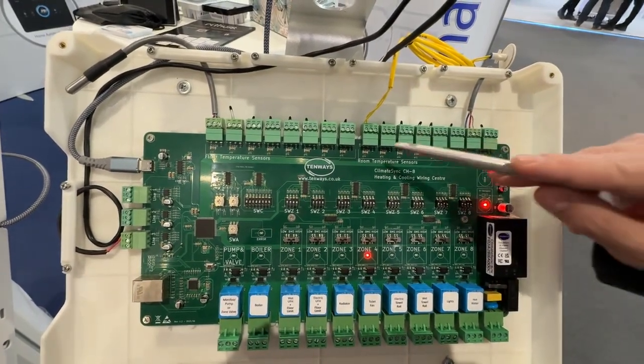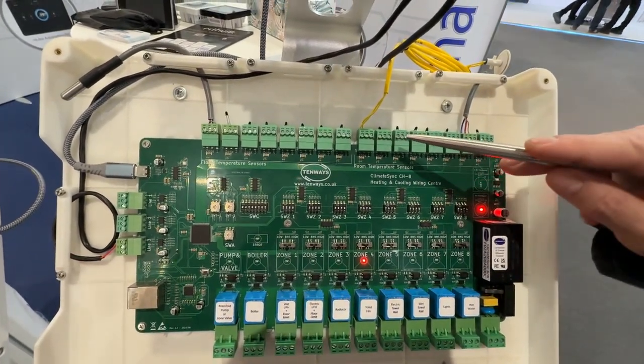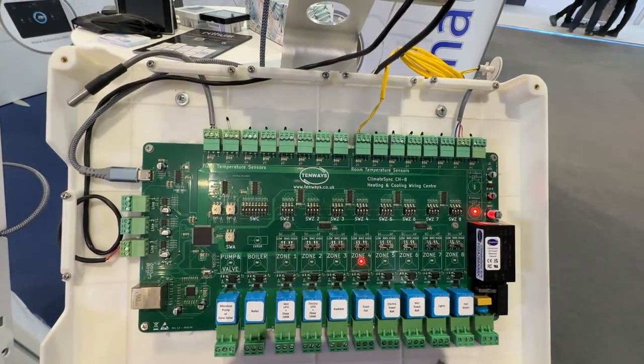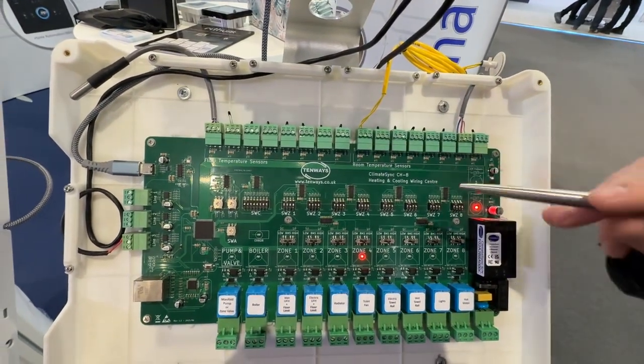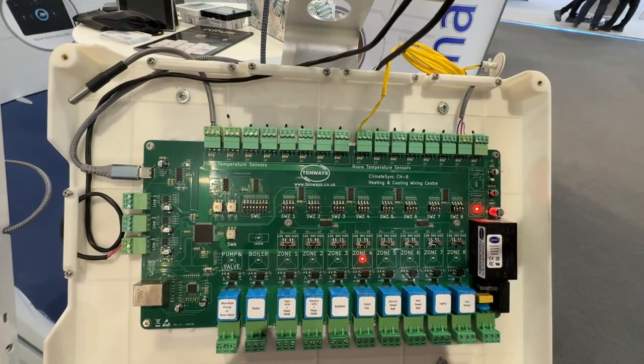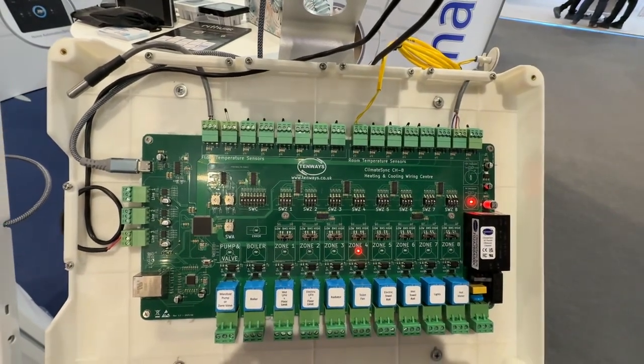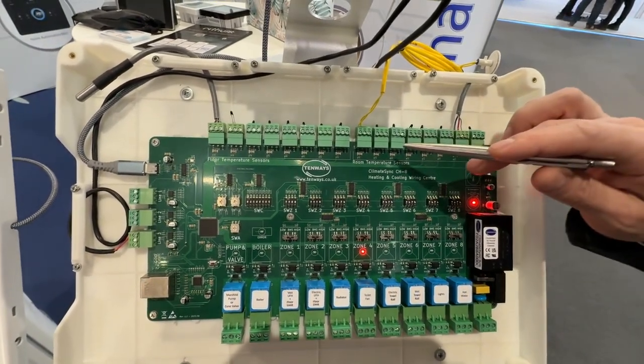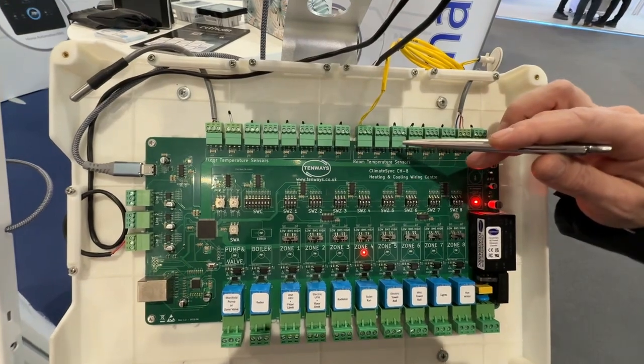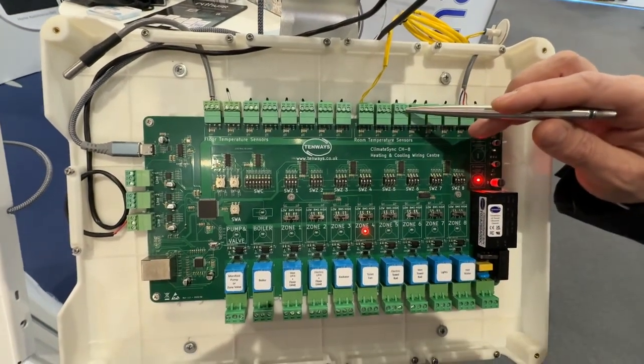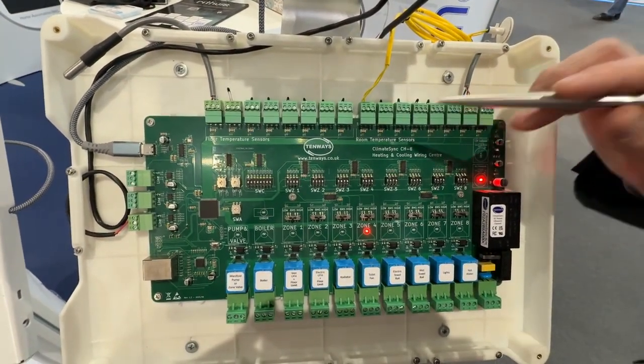The resistance of each sensor is NTC 10K by default. However, you can set it up for any other resistance such as 20K, 50K, 100K, etc. You can also set the beta coefficient of the sensor and therefore have precise temperature control for the temperature range you require.